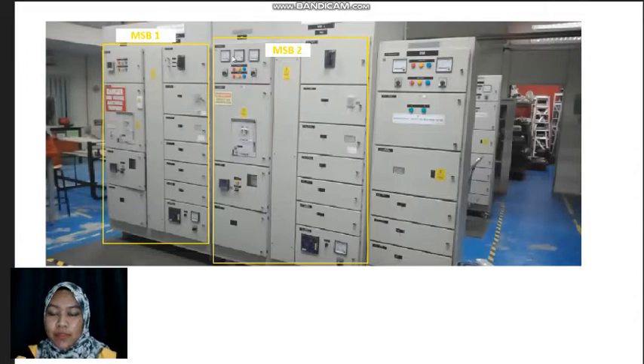I'm going to explain the procedure on how to turn on the LVSB. Before that, we must make sure that we wear all the PPE, check the safety measures, and apply the permit before doing the operation. We can see here that there are two sides, which are MSB1 and MSB2. We must make sure all the loads and air circuit breakers in both MSB1 and MSB2 are in off condition before we start the operation.